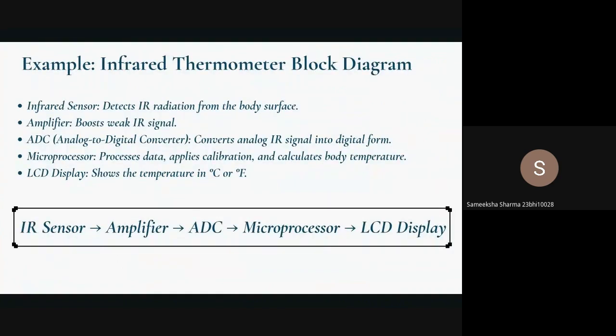Here I will take an infrared thermometer as an example. The IR detector senses radiation from the skin. That signal is amplified and converted to digital by an ADC and processed by a microcontroller, which applies calibration and corrections. The result is shown instantly on the screen.